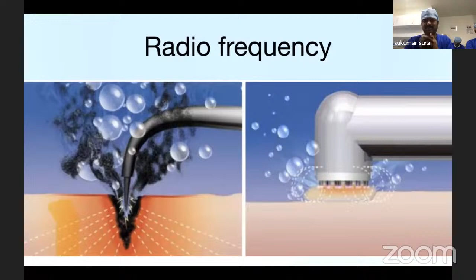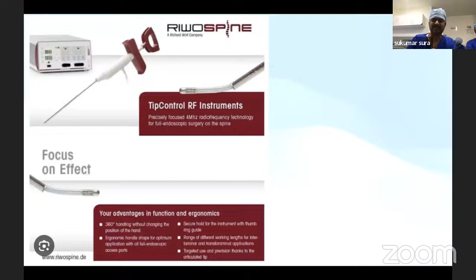And when you compare the radio frequency over electrocautery, I'll come to that in a minute. The radio frequency probe we commonly use is 4 megahertz. How does it differ from the electrocautery or bipolar cautery we use in our day-to-day practice? The bipolar we use in day-to-day practice is around 400 to 500 kilohertz, and the radio frequency we use is 3 to 4 megahertz. So it is almost 8 to 10 times higher frequency that we operate at in endoscopy. How does that help? The effect is very focal. The tissue spread of damage is very, very less. And as we are under irrigation, the effect on the tissues ultimately becomes one fifth of whatever it would be if we used cautery without irrigation.